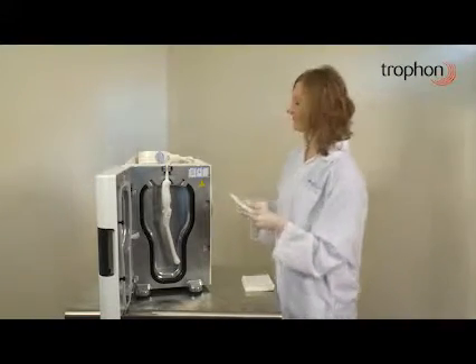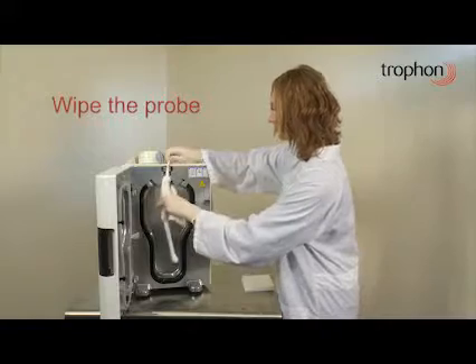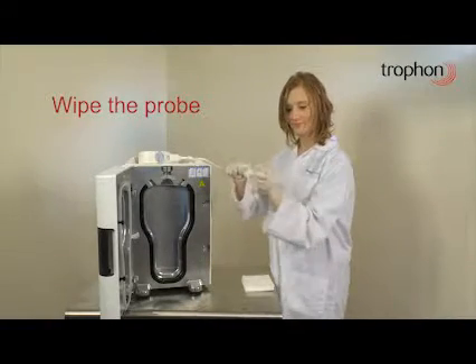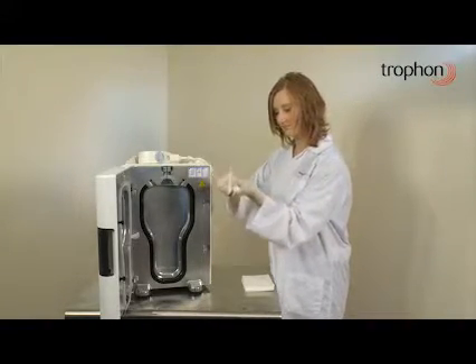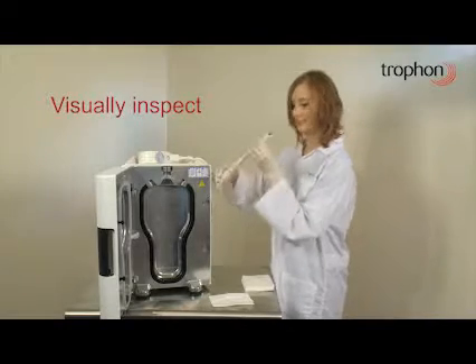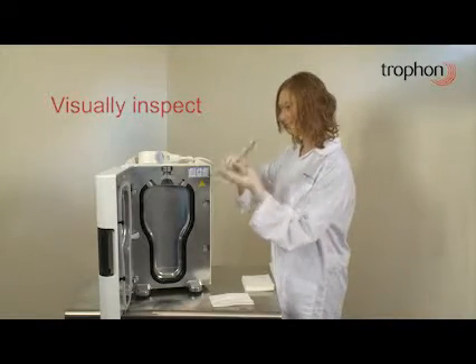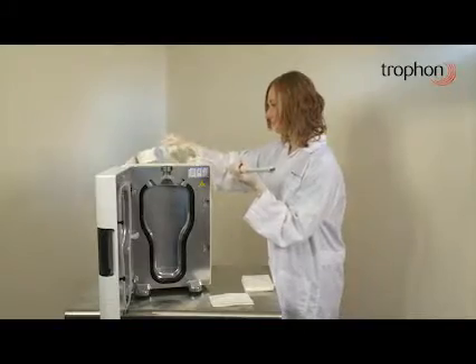Remove the probe and wipe with an absorbent single-use dry lint-free cloth. Visually inspect the probe and ensure it is dry. The probe is now high-level disinfected and is ready for use.